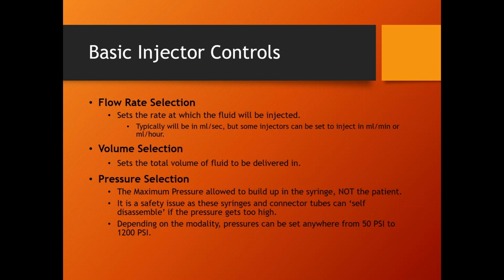All right. So for angio injectors, there's the injector system that goes on your X-ray systems. Because the image capturing procedure is so fast, sometimes we need a massive quantity of contrast right here, right now. All right. So that's why angio injectors can go up to flow rates of 40 or 50 milliliters per second. Okay. Whereas CT and MRI procedures, anybody ever had an MRI procedure? Those are like 20 minutes minimum. It's at least 20 minutes, half hour, 40 minutes, something like that. It's a very slow procedure.